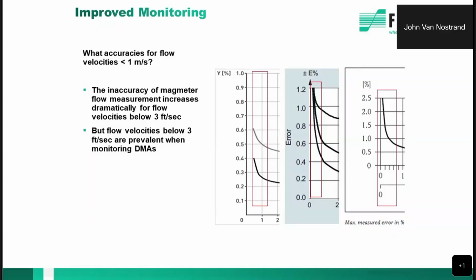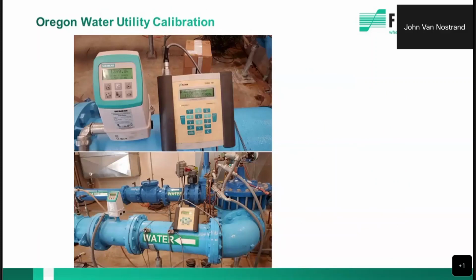That 0.5% is, like I said, ideal conditions from 3 to 33 feet per second. Most water systems flow below that. What's important to note is that the velocity that FLEXIM is able to capture goes down to 0.03 feet per second. So it's essentially 100 times less than the sweet spot for a magmeter. Hard to believe, but it's been proven over and over, and we continue to have great success with it.